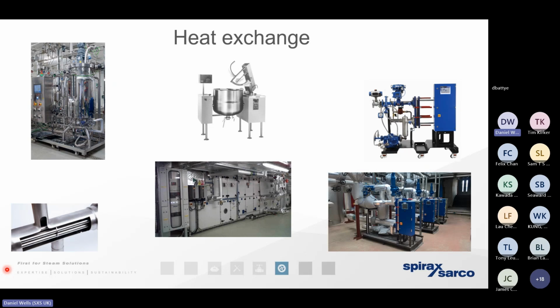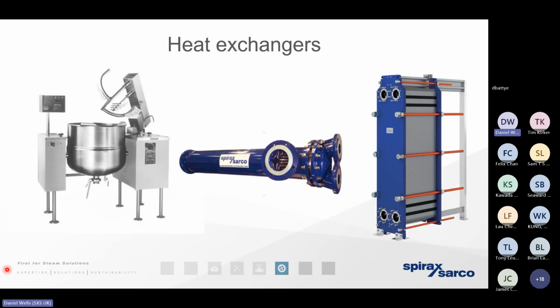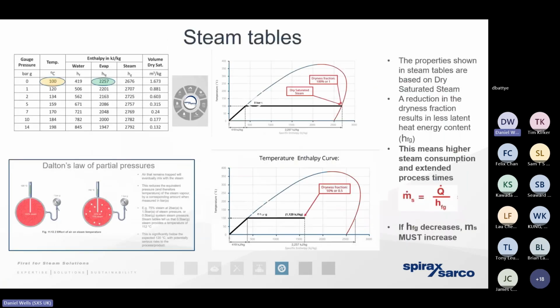And if we don't return the condensate, we appreciate the adverse effect that it can have, not only on the process itself by becoming a barrier to heat exchange, but also the effect it can have on inefficiency and maintenance demands by allowing it to be backed up into the distribution pipework. So those dreaded steam tables again, I keep coming back to them. You'll be sick of the steam tables by the time we've finished this series of presentations.